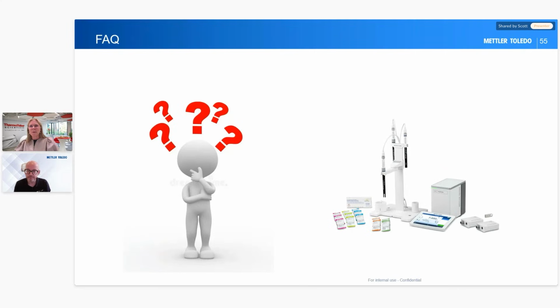Aurelie is asking, if we do a linear calibration for a buffer at pH 8, is it more accurate to use only 2-point calibration solutions, pH 7 and pH 10, than to do a 3-point calibration using pH 4 also? Technically, it would offer the same type of accuracy if you did a 2-point versus a segmented one. But it depends on the meter you're using. Some meters can't do segmented readings, so it's something you need to look at on your meter.